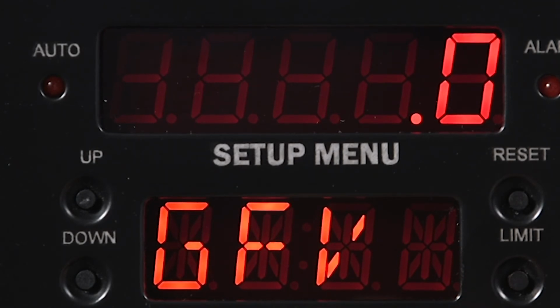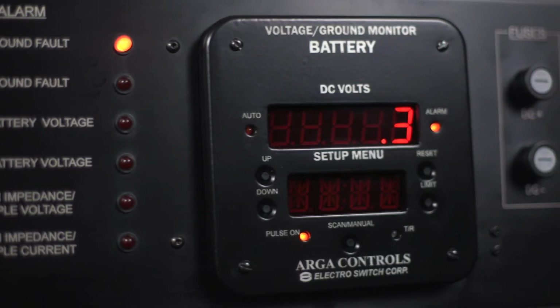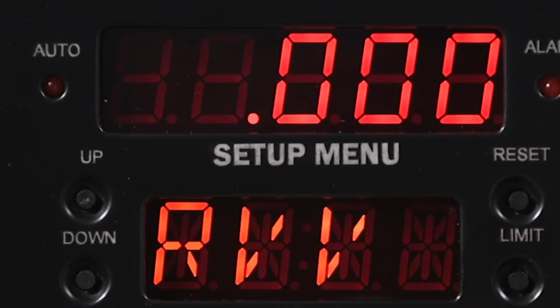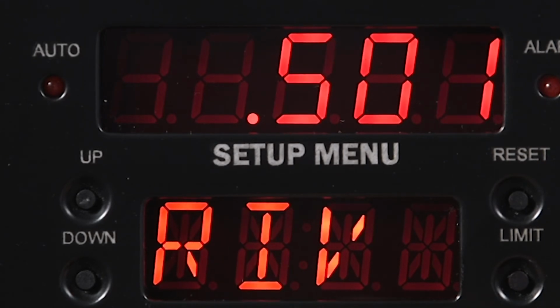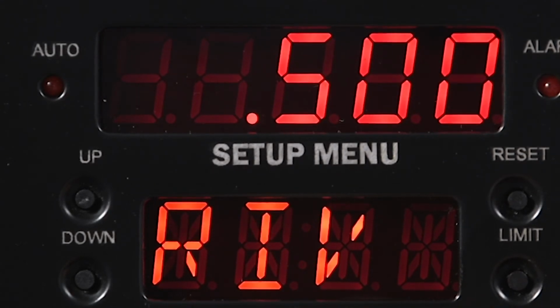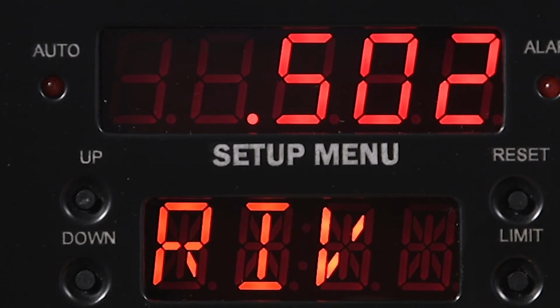If I did have a ground fault, there would be a voltage shown, and you would see a proportional change in the positive or negative voltages depending on the level of the ground fault. You will see that later when a ground is simulated. Next, you can see what ripple voltage is if you are monitoring the impedance of the battery, and then ripple current. This is to allow one to identify whether or not there is some degradation going on with the battery terminal connections, or maybe some other issue driving one to check the battery.